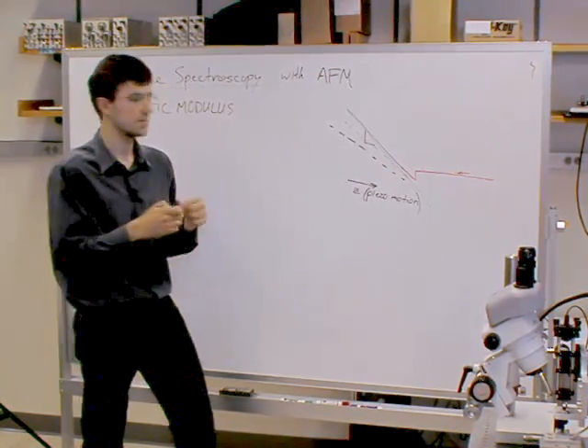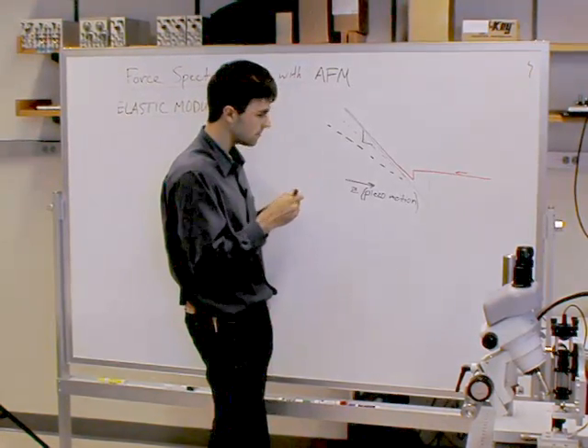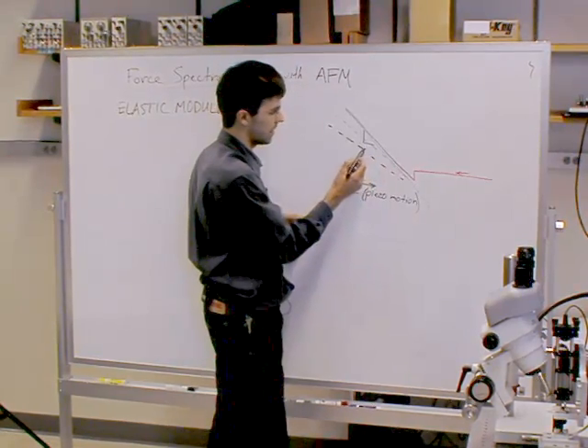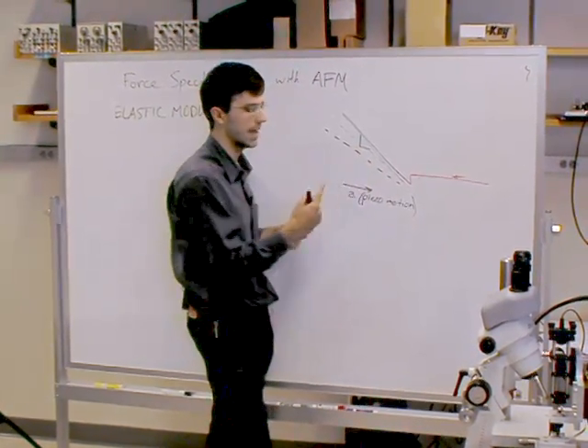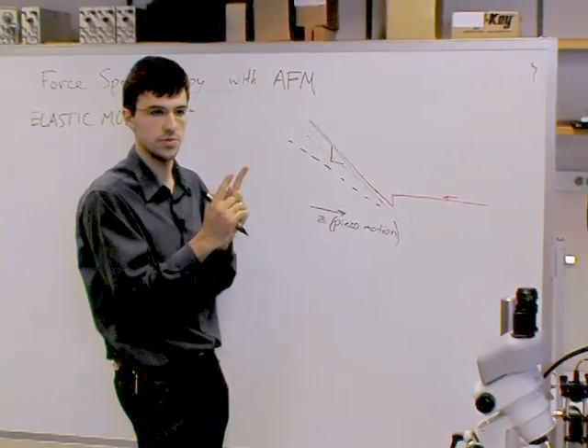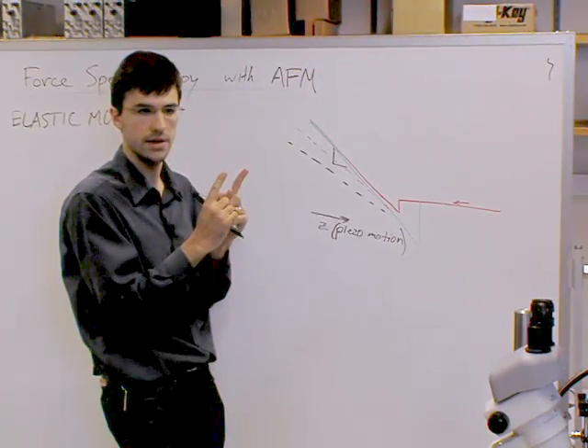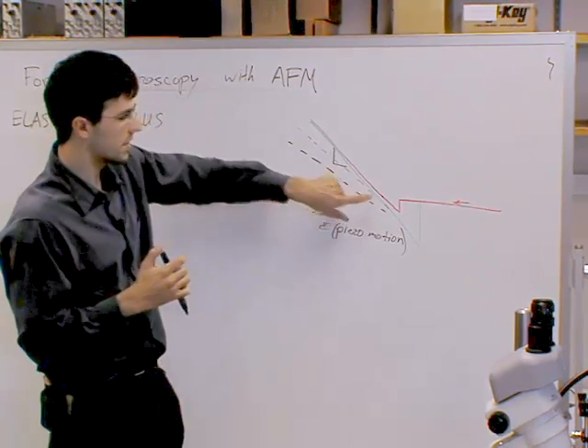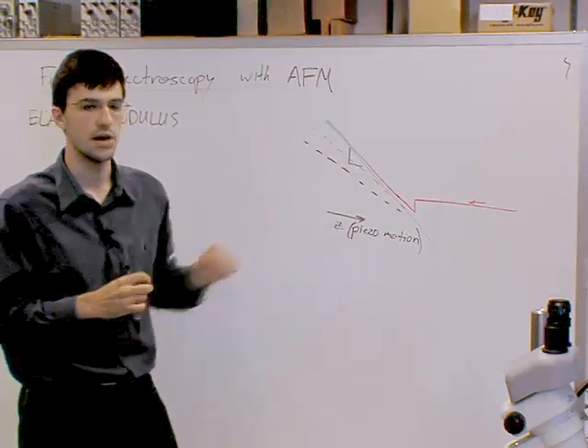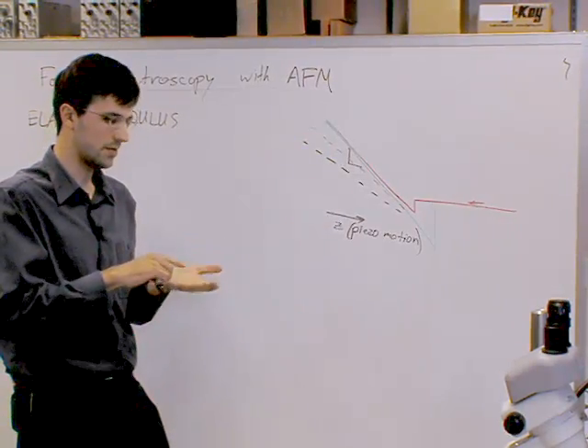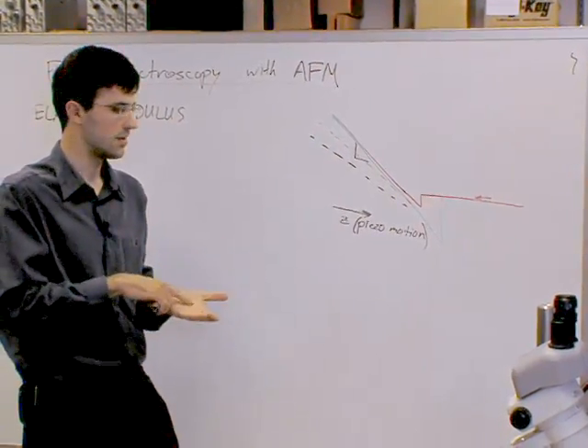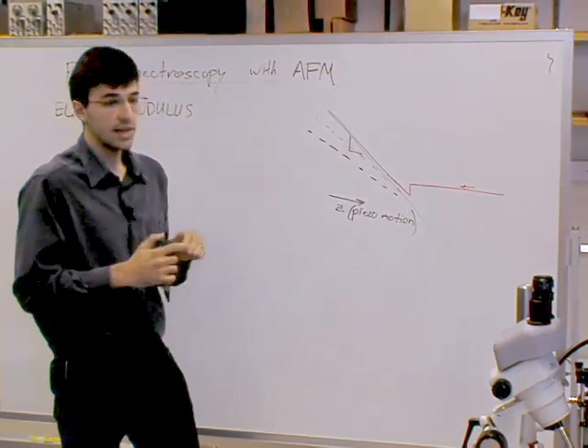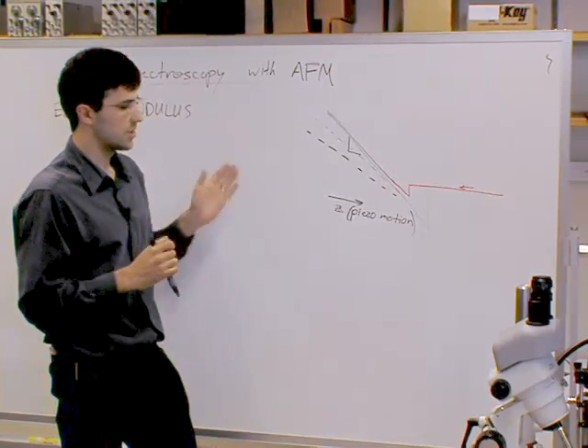But the idea is simply that a material that's compliant that you're going to be indenting with the probe will, as the stage moves, it'll deflect the cantilever less than it would if the material were hard. So the difference between the motion of the stage and the indentation of the cantilever will give you the actual distance through which the material has been indented. Does that make sense? So let me say that again.